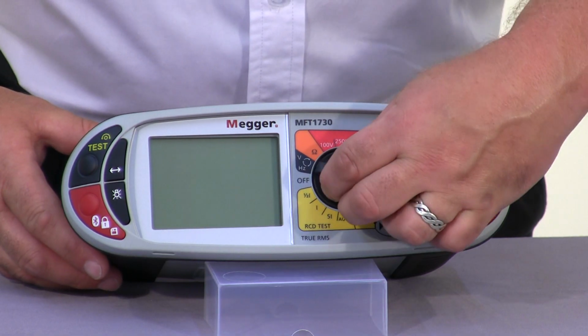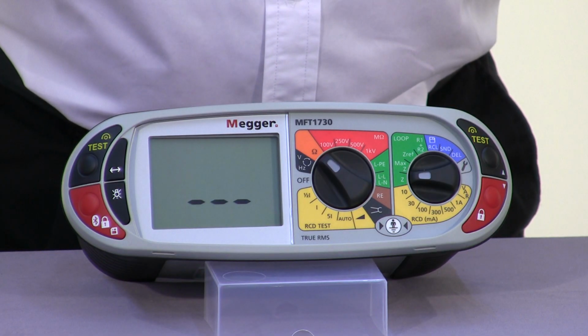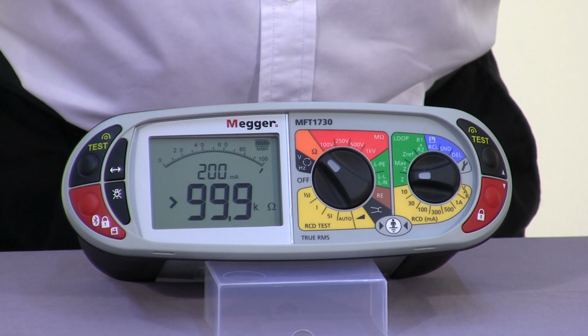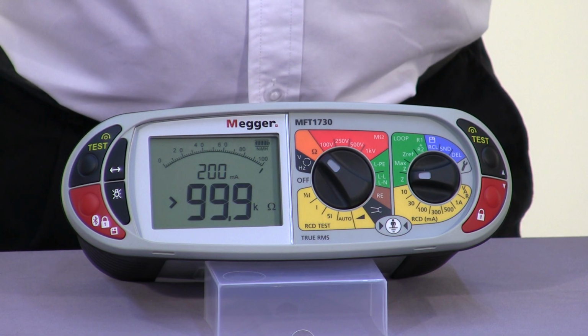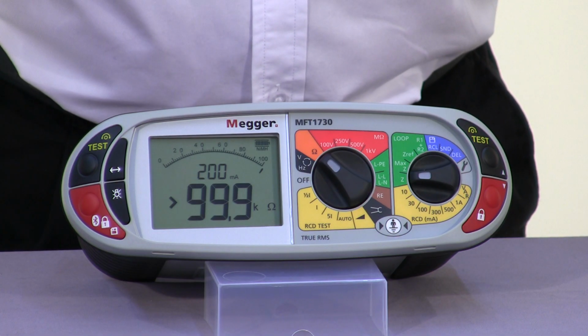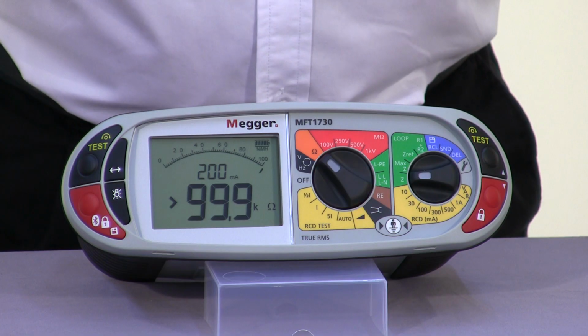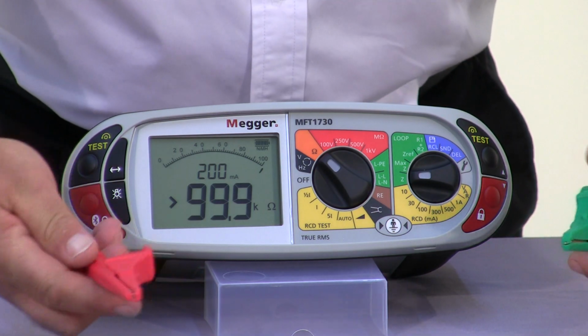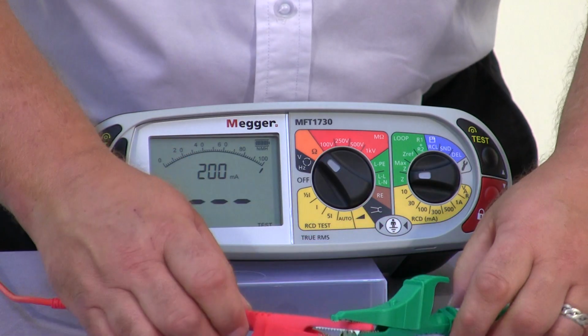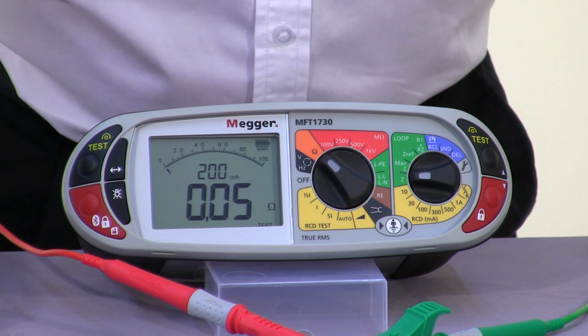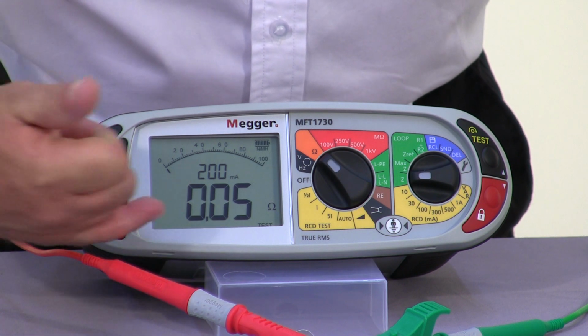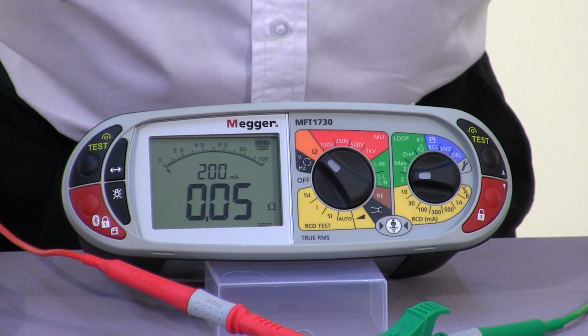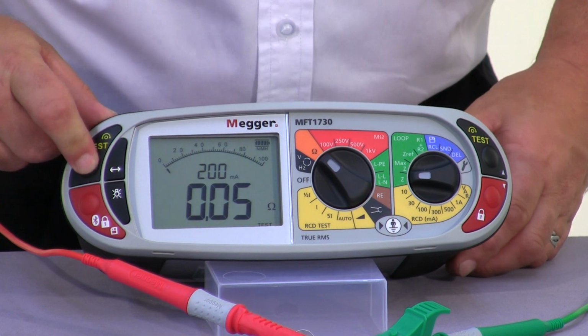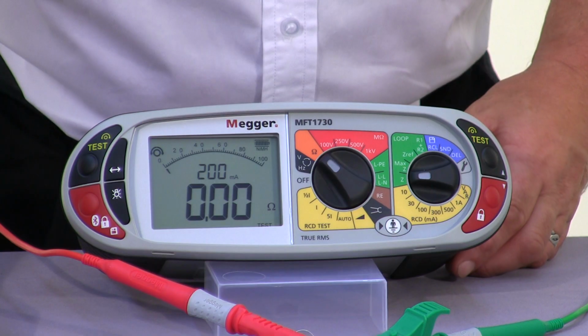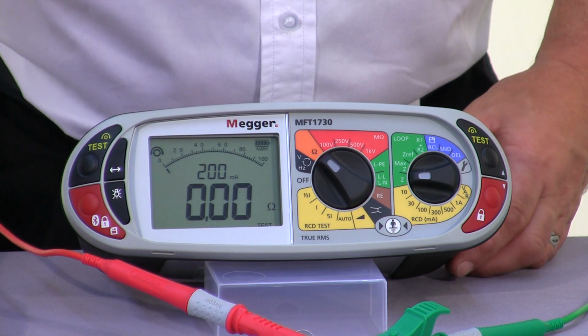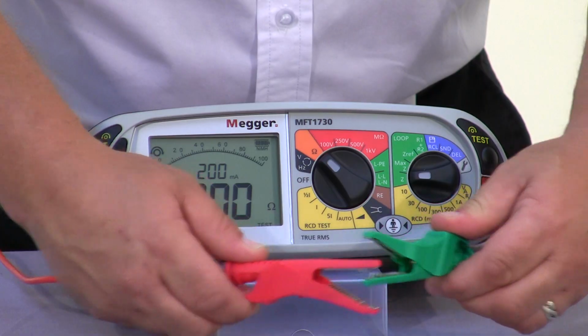Okay, selecting continuity measurement, the first thing that we'd need to do is look to null out the resistance of the lead set. One of the features with the MFT1700 series and the Megger range of insulation continuity testers is the auto start. So as you see, when I connect our leads together, the unit will start the test automatically. Now, you'd heard there that we've got an audible indication, and it's confirming that we've got a stable reading. So now, pressing the test button, this will actually take in the compensation of the lead null, and we get an indication on the screen to confirm that the null is in place.